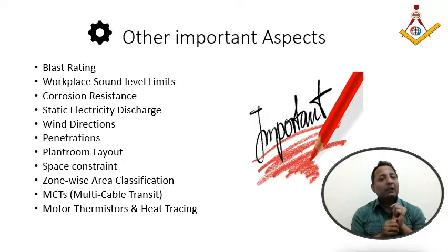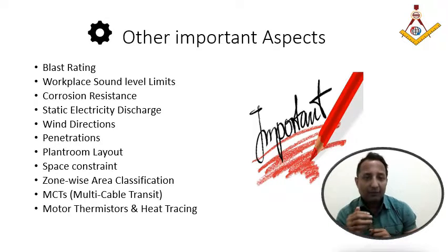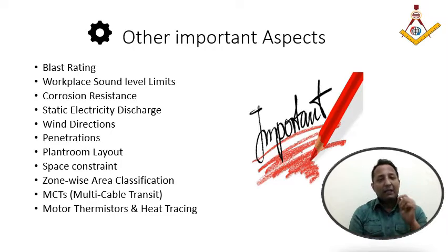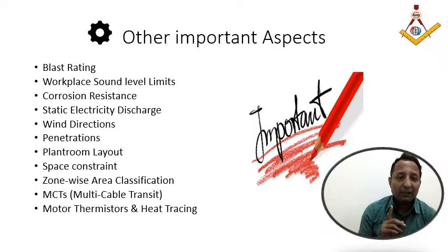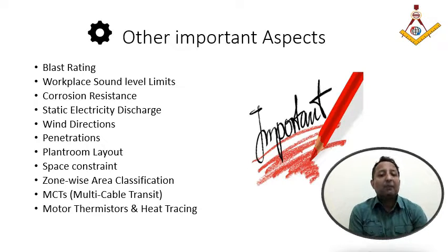Now let's come to static electricity discharge. This point is very important because as the relative humidity at the surface drops below 30%, static electricity gets generated over the surface of the equipment. You might have seen that in harsh winter, if you touch any metallic object, you get a static electricity current. The reason is static electricity gets deposited in extreme dry environments, and that can play havoc if earthing is not done properly. So static electricity discharge is also a very important factor while designing the system.